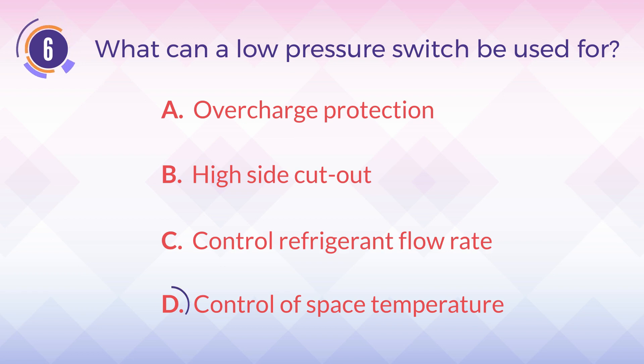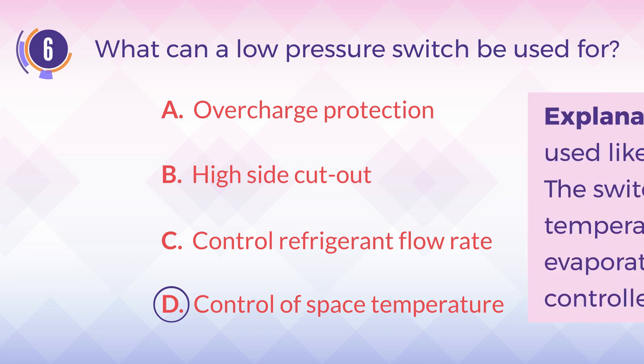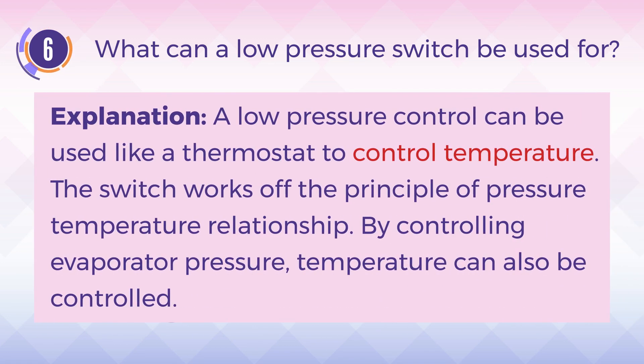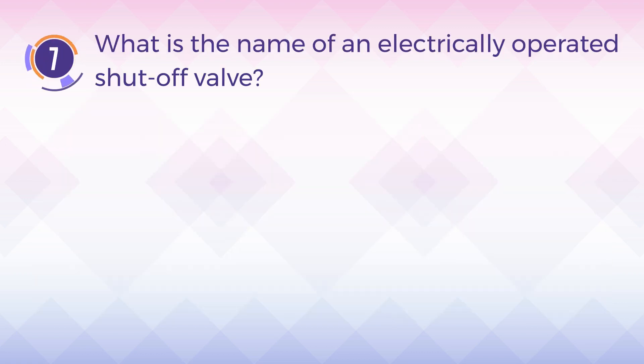The answer is D, control of space temperature. A low pressure control can be used like a thermostat to control temperature. The switch works off the principle of the pressure-temperature relationship; by controlling evaporator pressure, temperature can also be controlled.